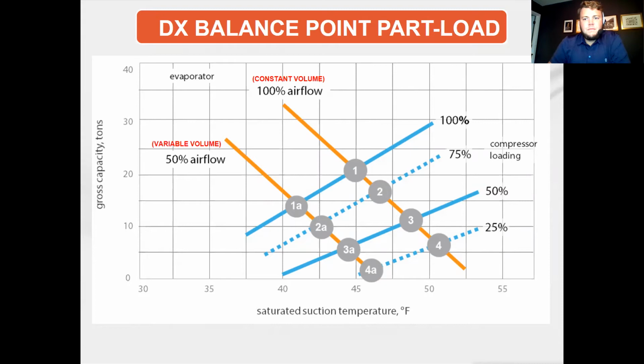So what we see is when we get way over to number 4 with just one compressor running, the suction temperature is raised quite a bit, and the leaving air temperature will have risen with it because we're at less capacity. What this means is that we're not going to have as much dehumidification as the design point.